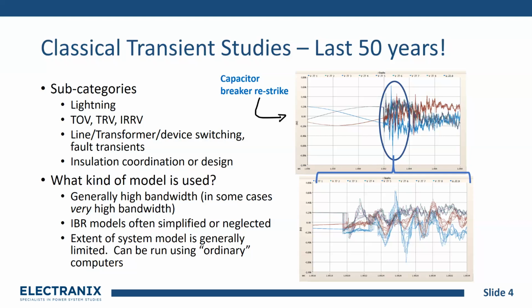I've got a picture on the right-hand side here of what it looks like when you have a breaker capacitor restrike. Essentially a breaker fails to operate correctly, and you get this transient. You get a very fast transient that rings down the line. The plot on the bottom is a zoom of the plot on the top, and if you look at the voltage all along a transmission line, you can see how that transient propagates down the line and reflects and bounces in different ways, and also interacts with the transients bouncing around on the other two phases, the normal phases.